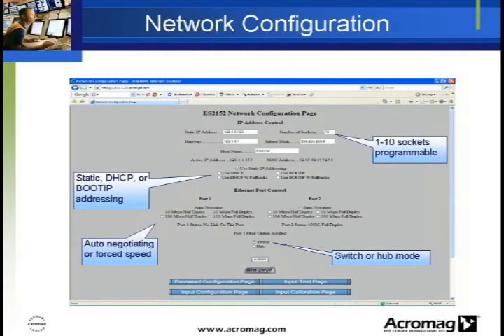As with other network-capable Acromag modules, the ES2151 and 52 modules are configured and set up through a simple web interface using your computer's browser, so there is no need to install or maintain any software. The ES2151 and 52 modules support up to 10 sockets, meaning each module can handle up to 10 masters, allowing 10 concurrent users to talk to the device. The number of sockets allowed is programmable as well, allowing the number of masters to be limited to just one or a few for added security.